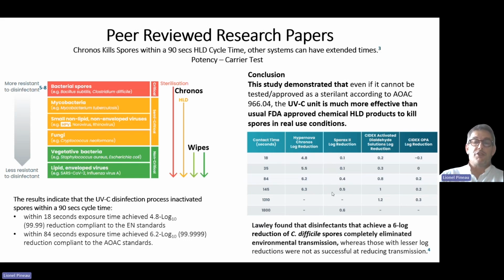According to the study we have published in 2022, we clearly demonstrate that the UVC disinfection process inactivated spores within 90 seconds, with a 6.2 log reduction within only 84 seconds. Furthermore, this study clearly indicates that the UVC unit was much more effective than the usual FDA-approved chemical high-level disinfectant product to kill spores in real-use conditions. So another time, we demonstrate that the UVC disinfection process can achieve the same efficacy level and even more on bacterial spores than a chemical disinfectant.